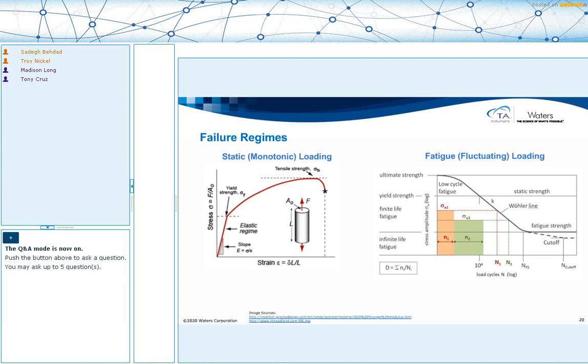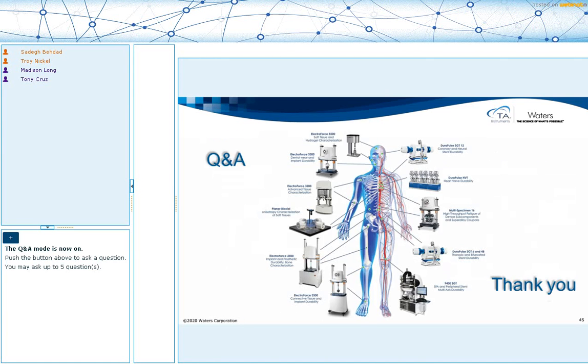On the machine itself, we have what we call the block waveform, which allows you to have various waveforms. Say your material starts with a sinusoidal waveform, then experiences a triangular waveform, meaning the stress now changes linearly up and down. Before that, it was sinusoidal. So you can create a combination of these and even apply conditional statements, saying, okay, if you are applying this load and you see that the material deformation is now reduced below a certain level, stop doing what you were doing, go to the next step and do this. That way you can create more complicated waveforms to replicate what's actually happening in the human body. And we are doing that in a lot of examples. Say, we have examples where people are looking at the effect of the human walking waveform on something.